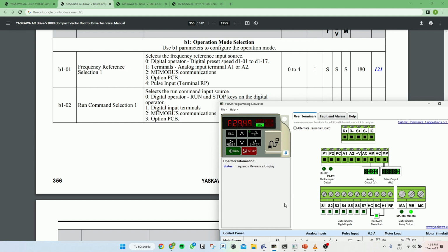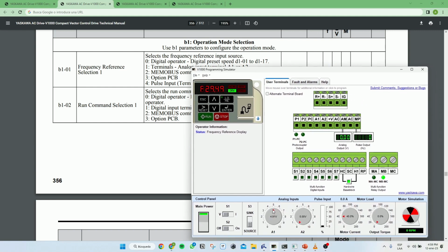So something else that we can do is that we can change the speed very easily. Do you see this? That's why I'm telling you guys that you need to be very careful in leaving this potentiometer for your customers. You need to protect your limits. Protecting your frequency, your velocity limit, so that it's not as easy to modify.